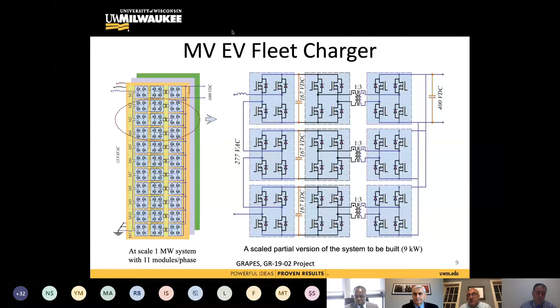In addition to that, you have 1000 volt, you have series input. One of the issues that we have with power electronics is that our current and voltages are not there for us to directly connect to 13.8. So that's why we are using this 11 level converter using silicon carbide devices, and this uses 1700 volt commercial devices. Then the zoomed in version you can see on the right hand side, where we are trying to build this at the lower voltage, when single phase 480 comes in and then 400 volt DC goes out, and there are 3 levels and you build each level. So what it really offers is isolation, mobility, control, and many other benefits that you can get from this setup. And at the core, again, you see it has a dual active bridge.